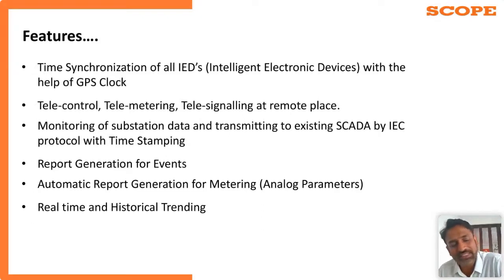Yeah, normally the latest protocols for substation automation or electrical systems are mainly the 61850 protocol. That is for substation communication, like from relay to RTU or relay to SCADA system, within the local SCADA system, where you should go for the 61850 protocol. But when it comes to the RTU sending data remotely to the SCADA system, you may require the 104 protocol.